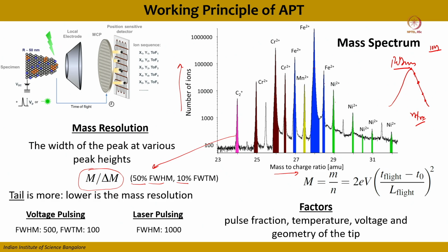In the laser you are actually heating the sample. When you do each pulse, there will be an increase in the temperature, and as soon as the second pulse comes, the temperature has to come down. If the temperature doesn't come down with the second pulse, usually you will develop a thermal tail in the peak. So you will get a large peak and a thermal tail.